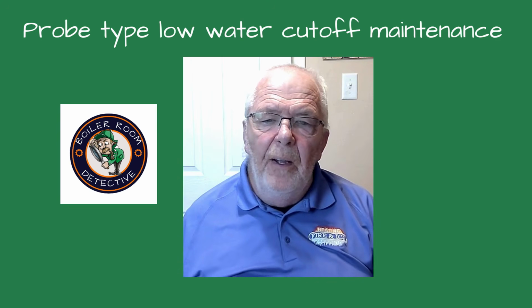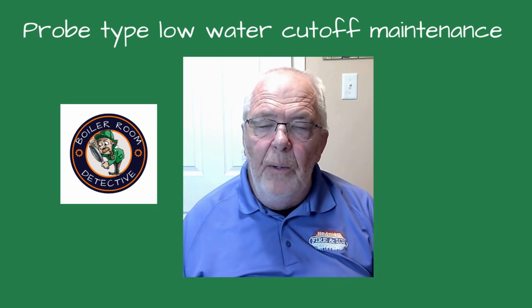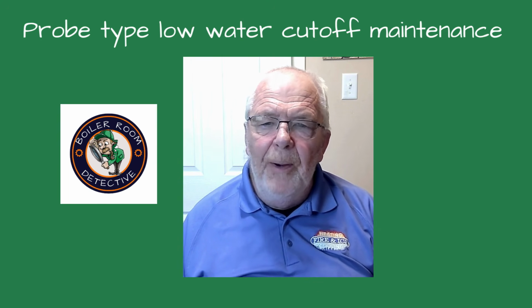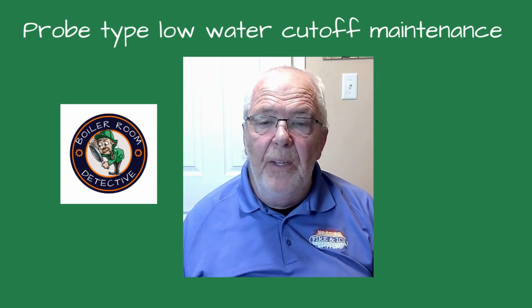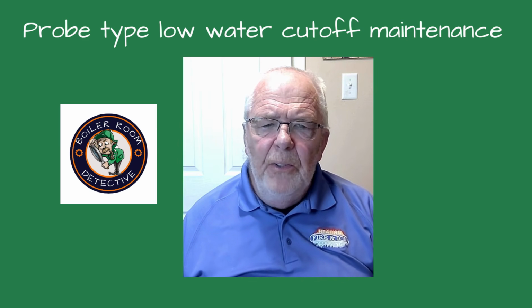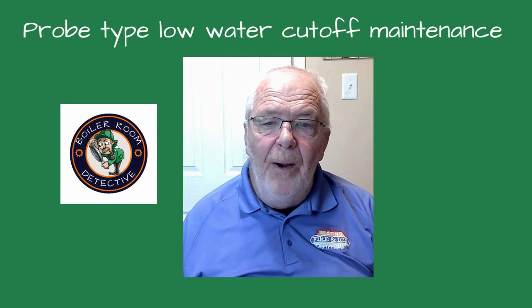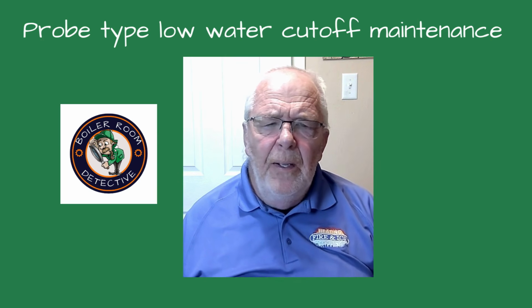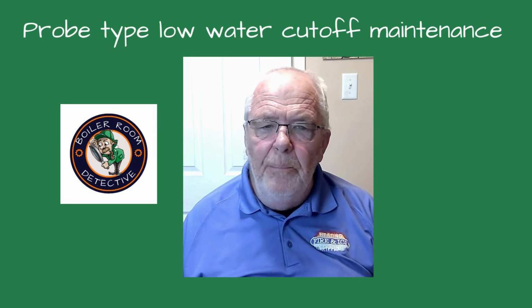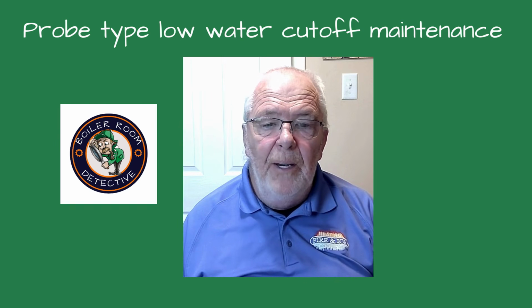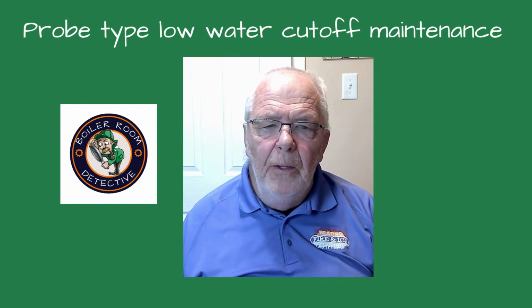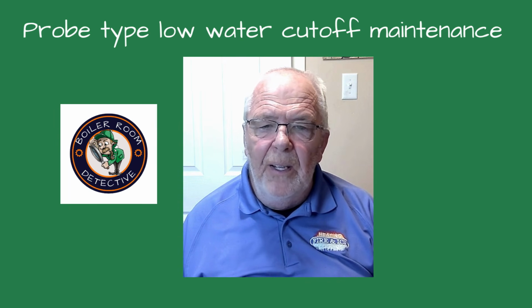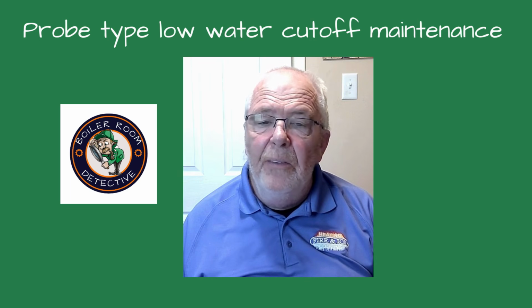They sit unassuming on the front or side of the boiler, a black or green box that almost blends into the background. Most owners or techs just ignore them, but the probe type low water cutoff requires yearly maintenance. It's not as involved as a float type, but it still needs regular maintenance. Did you know the low water cutoff is a leading mechanical cause of boiler accidents?